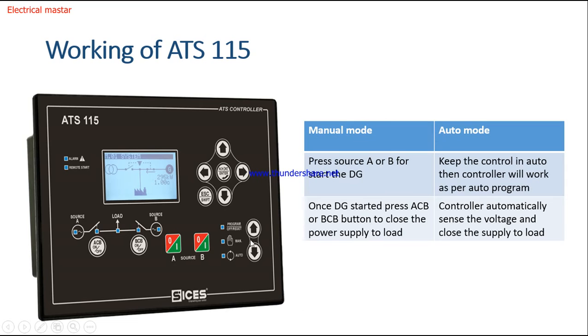For the auto mode, you just put this LED into auto by pressing this arrow key. That's it. No need to do anything else. The ATS itself automatically checks whether the main supply is available or not. It always gives preference to the main supply. If main supply is available, it will automatically close the ACB and the load will be connected to the main supply. Whenever the main supply is not available, it will automatically open that ACB, send the start command to the generator, and close the BCB breaker to the load. Everything is in complete auto mode. This is the way the ATS 115 works.